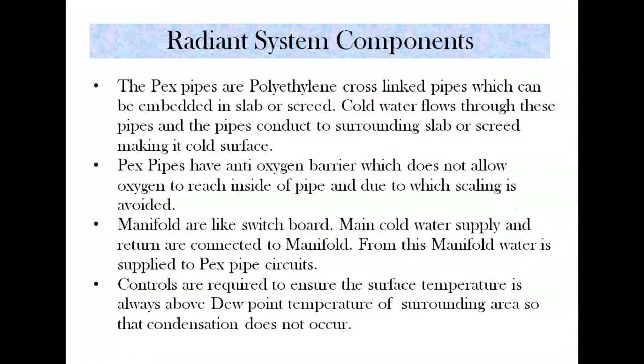9 mm is used in a gypsum ceiling, where the pipes are embedded in the gypsum panels that are used as a ceiling. The 16 mm is used for the underfloor. I'll come to what the underfloor system is. It is inside the slab, so that it occupies less area inside the slab. So 16 mm and 20 mm are the commonly used pipes either in the underfloor or inside the slab.